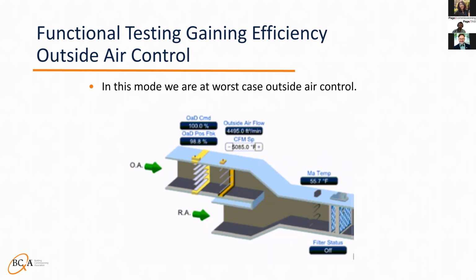If the unit cannot maintain max set point, how can we fix it? There are a few ways this is done, and some fixes happen to grind my gears, like modulating the return air damper inverse of the outside air damper. Don't do that. The best way to do it is to only start modulating the return air damper once the outside air damper is 100% open and cannot maintain its set point.